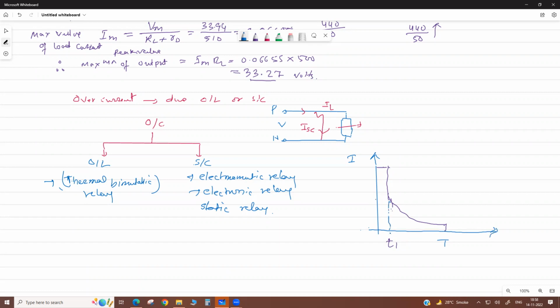This is minimum definite time tripping. But sometimes, for this type of current, it takes some time. Suppose this is your full load current, but it is increased like here only. Then it gives this delay time, like overload, due to overload. Very high current in a very short time trips instantaneously. But if it is an overload, then there will be a time delay.